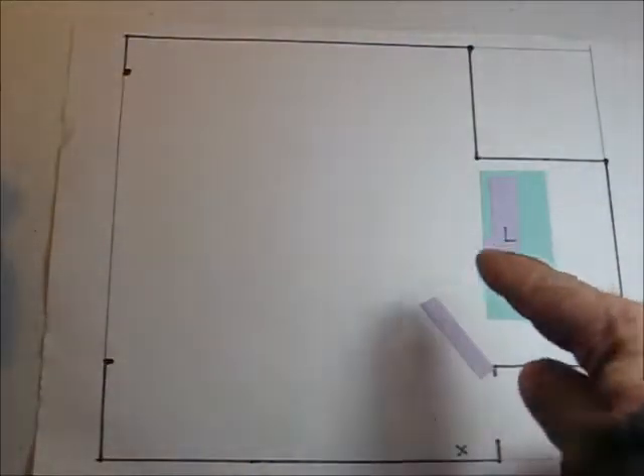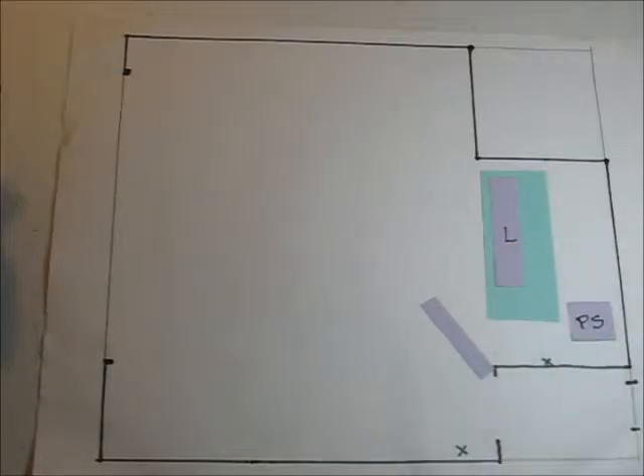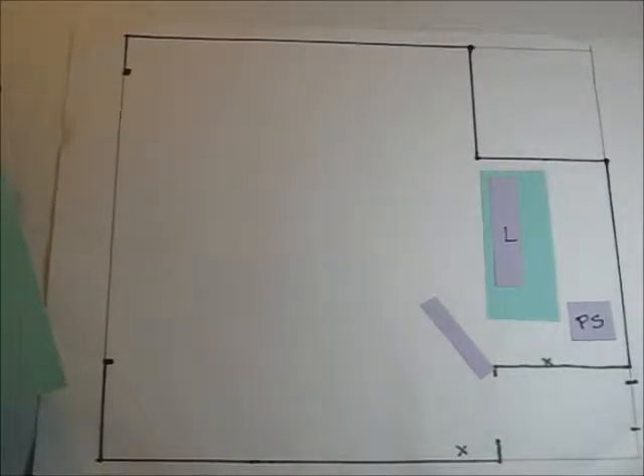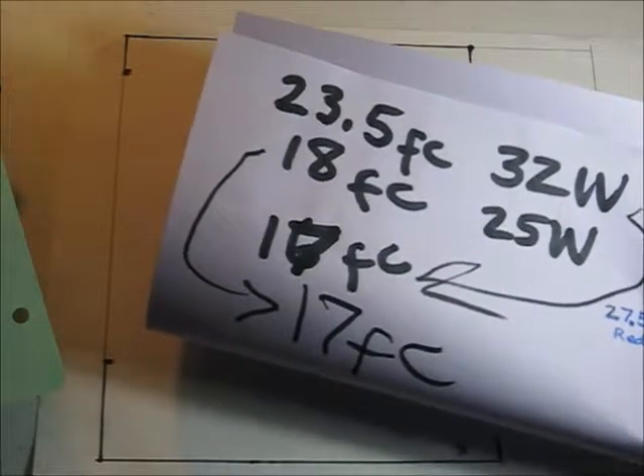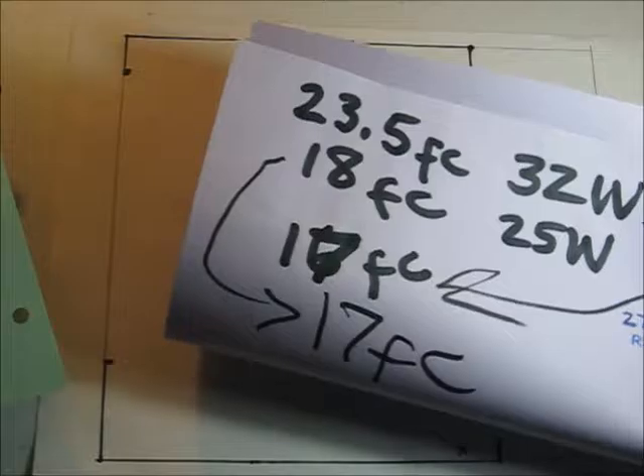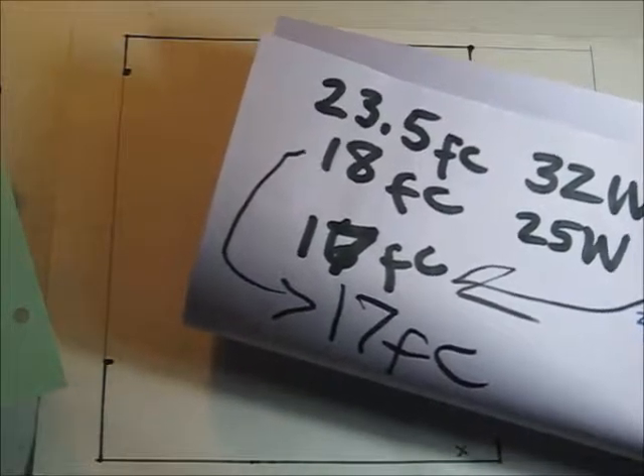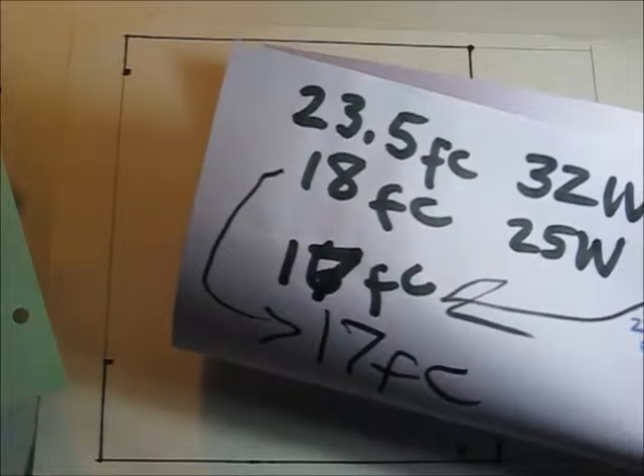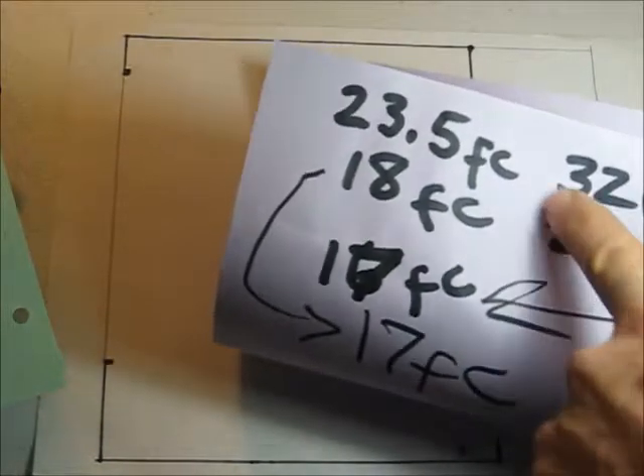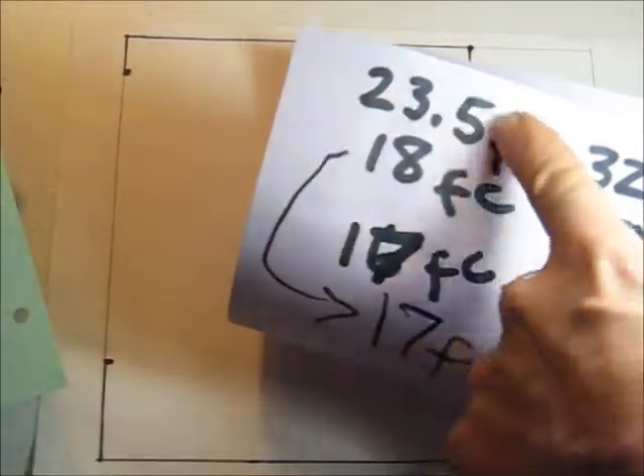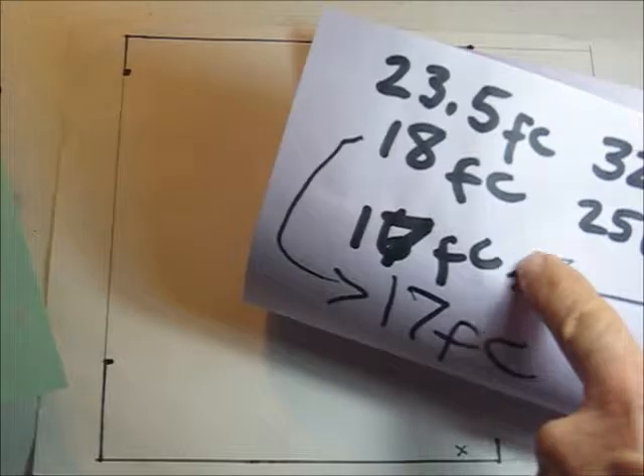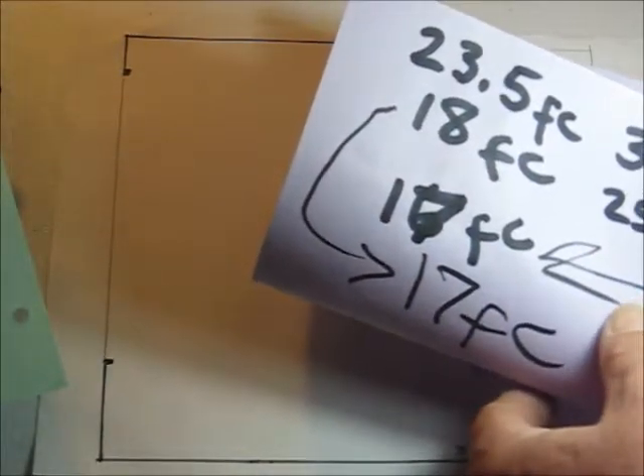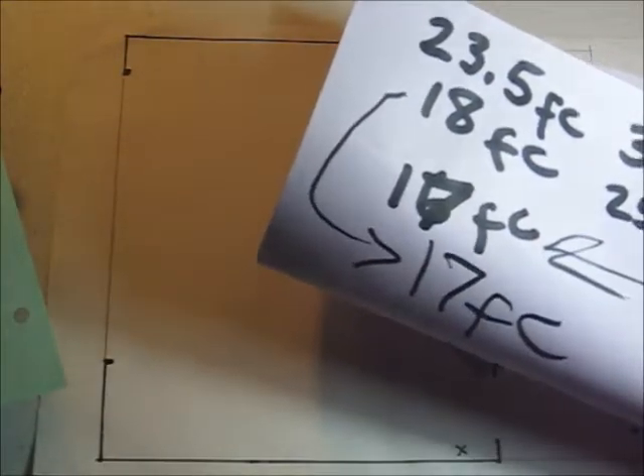We are going to take some 32-watt lamps in this 0 to 10 volt dimming ballast, and we are going to tune it down. And then we are going to replace the 32-watt lamps with some 25-watt lamps to simulate dim down and yellowing over time. We'll have to tune the 32-watt lamps down, which were giving me about 23.5 foot candles, to below what the 25-watt lamps give me, which is about 18, and we hit it at about 17.